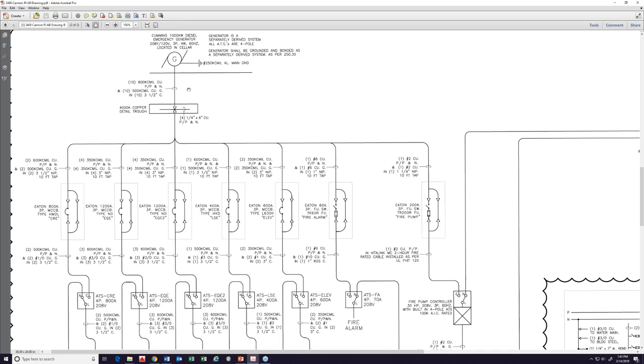No question about that. And then one last one, as far as the follow-up on the generator, do we need a main breaker when we have more than six switches? No, absolutely not. The six disconnect rule of Article 230, if I remember correctly, 71, does not apply to a generator. Please remember that in Article 230, the definition of service is only utility service. Any other source, such as a generator, a solar system, a wind, or anything else, is not service.